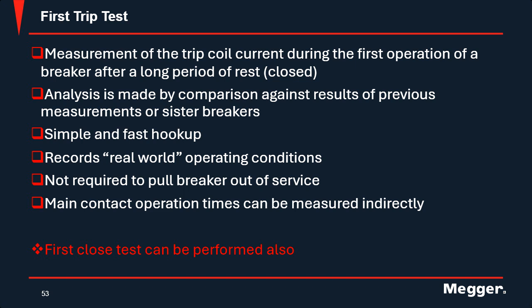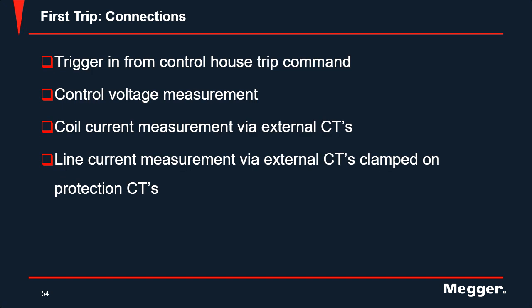You can also do a first close test if the breaker has been left in an open state for a long time and you're trying to close it into a live line. You can also do a first close test as well. So how does it work?